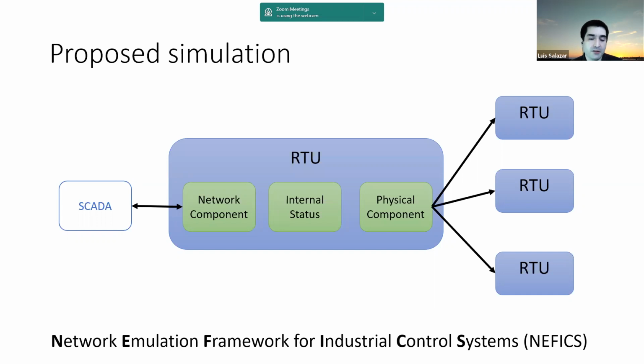You have an RTU with three main components. The network component handles all the IEC 104 related stuff: the control station process, the states of that process and the timeouts, and it understands the IEC 104 packets, encapsulating the data exchanged with the SCADA, and understands and executes the commands received from the SCADA.